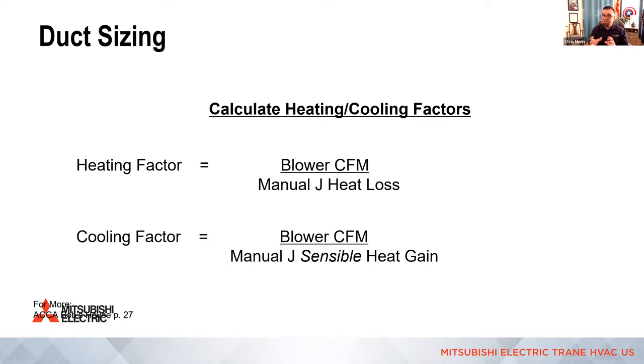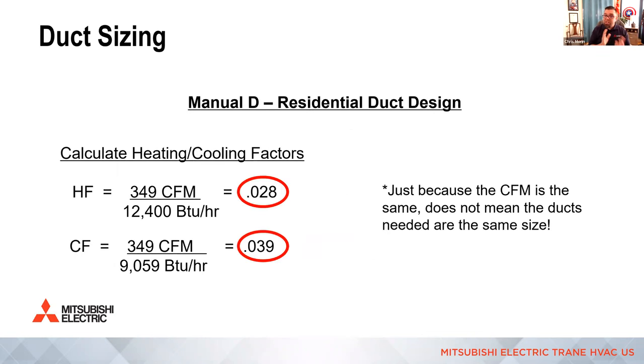So this is where people start to make some mistakes. Really important, you remove the latent, and that's why most Manual J software reports separate latent and sensible, and then of course you add the two together and that's your total, right? So in this particular example, we'll get that 349 CFM that I had on that first page from the submittal for the SEZ one ton. That's the top side of the equation for heating and cooling, right? Because it's the same volume of air.